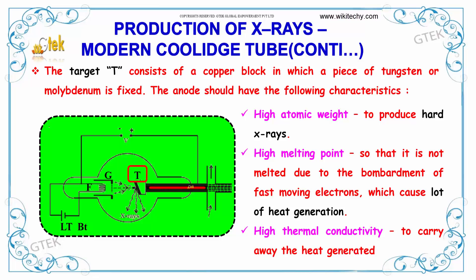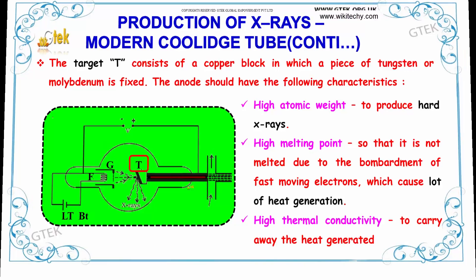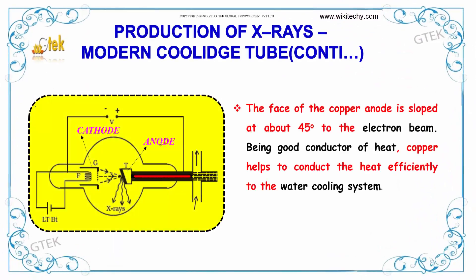This is the target T. The face of the copper anode is sloped at about 45 degrees to the electron beam. Being a good conductor of heat, copper helps to conduct heat efficiently to the water cooling system.